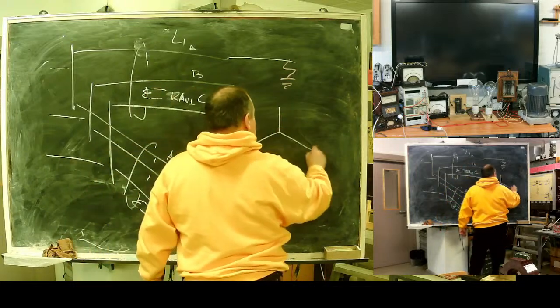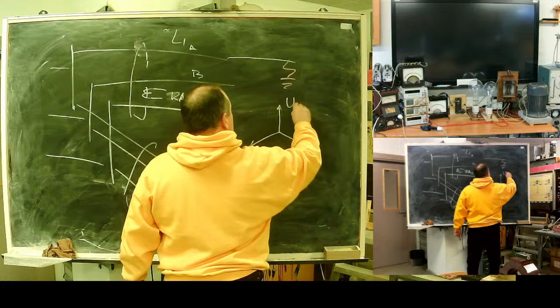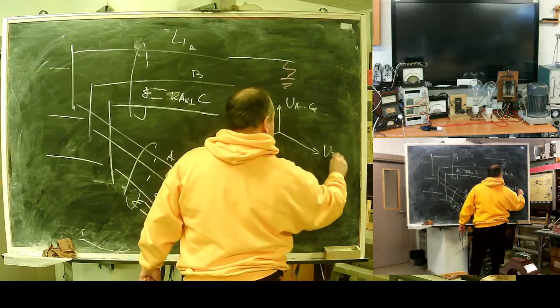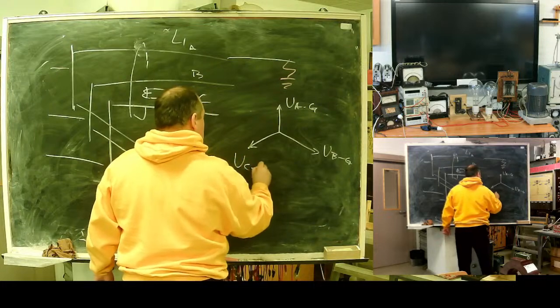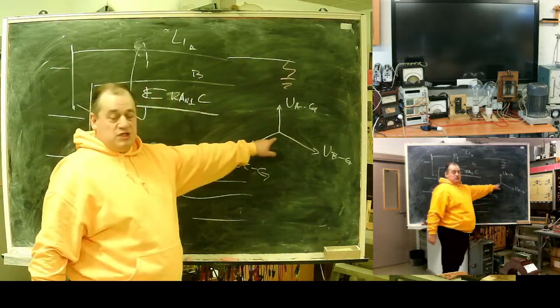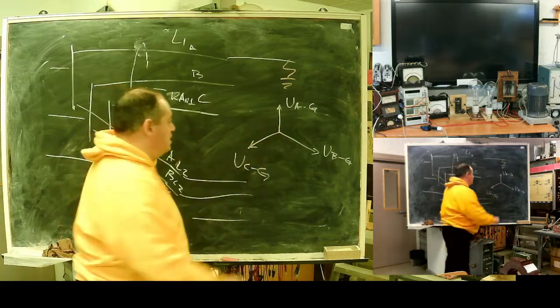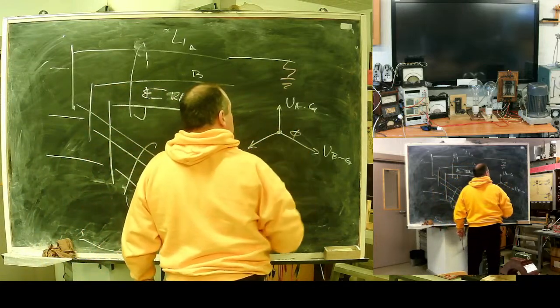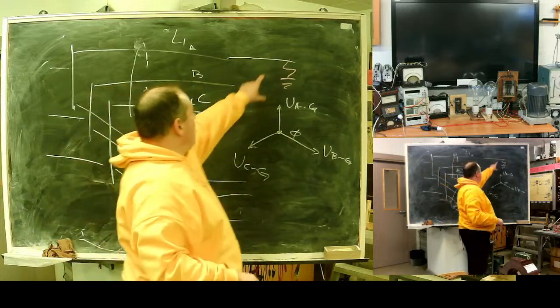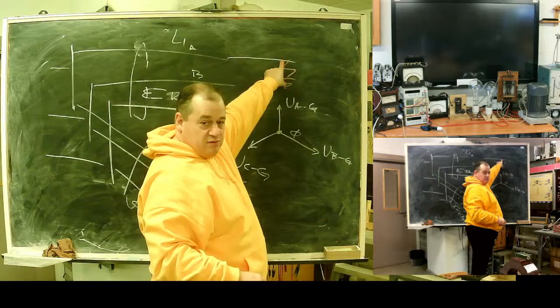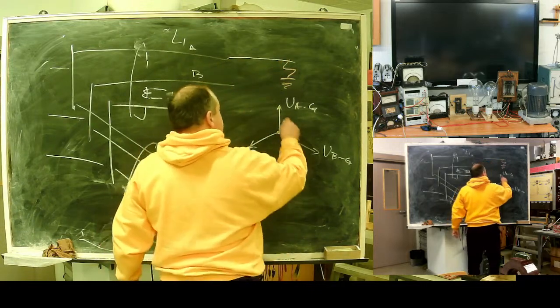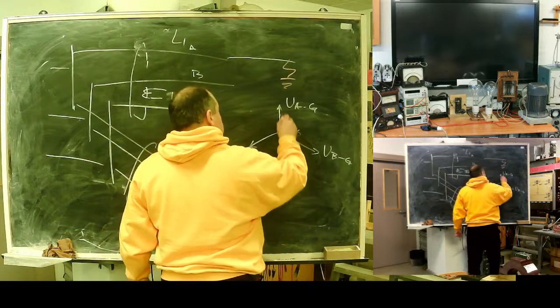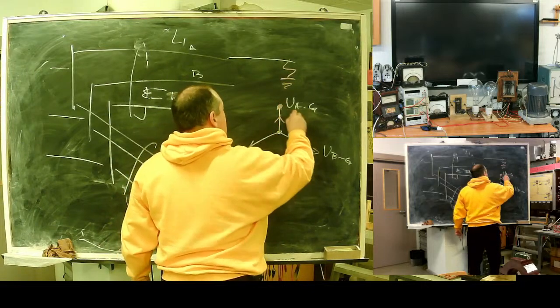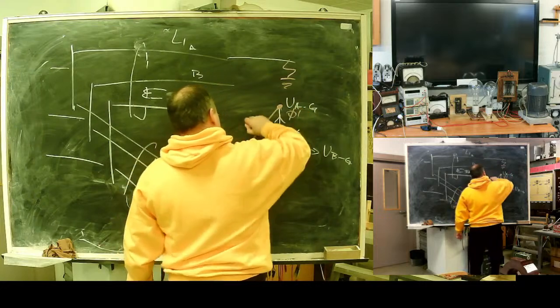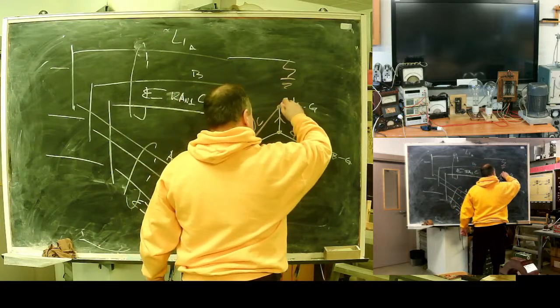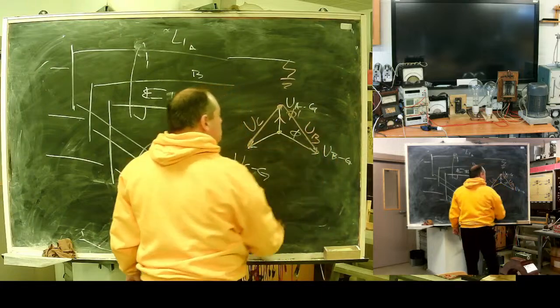I will draw it again. Before the fault, a ground voltages relative to ground looked like this. Here was our zero or neutral point. At the moment A phase connects to ground, what happens? Zero point goes here. And this will be C voltage, and this will be our B voltage after the fault.